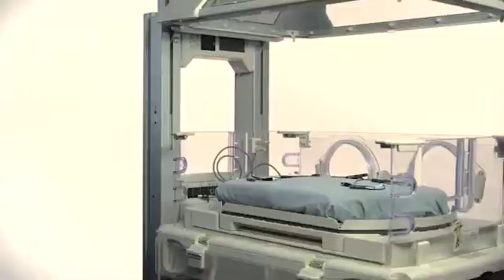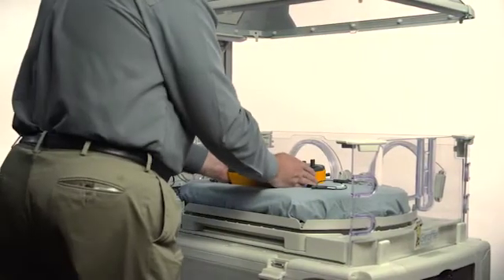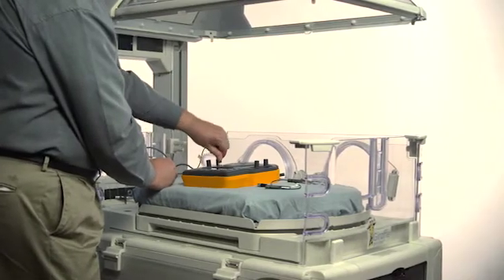The INCU-II has onboard automation and comes with a miniAnswer software plug-in. To start, place the INCU-II in the incubator or radiant warmer you're testing. In this scenario, we're going to test an incubator.